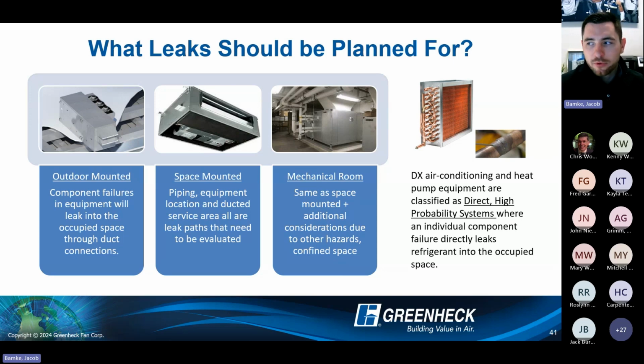Okay, so A2L refrigerants. That is that safety classification, and the main concern here is they are mildly flammable. So the big concern is what kind of leaks might I see and how should I plan for them? There's three main types of leaks that we're looking at when it comes to equipment classification. First one is outdoor mounted equipment, and that is where you're going to see component failures within the equipment that will leak refrigerant into the occupied space through the duct connections. Next one is what happens when equipment's mounted in the space itself. Well, now you have additional piping, you have equipment location, and then you have still that ducted service area that are all leak paths that need to be evaluated.